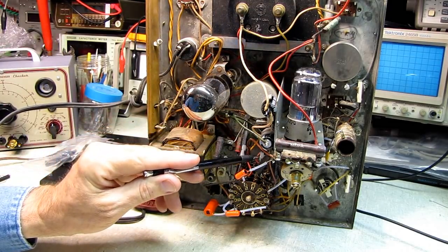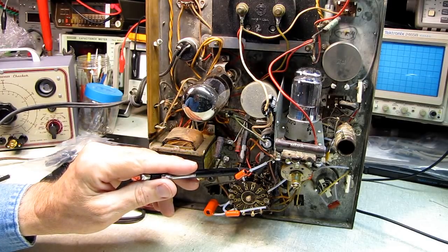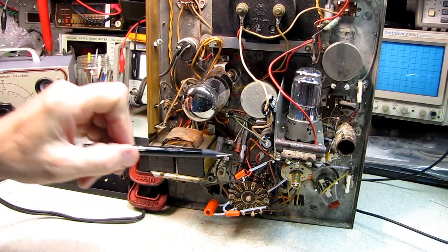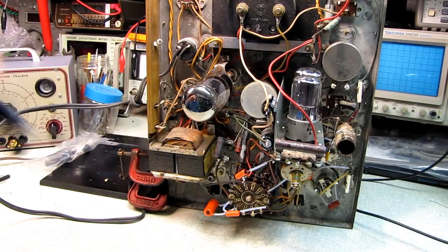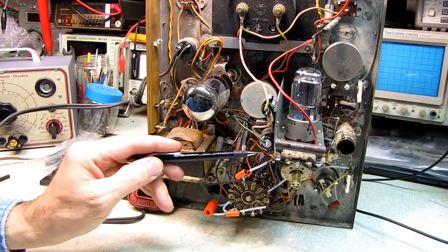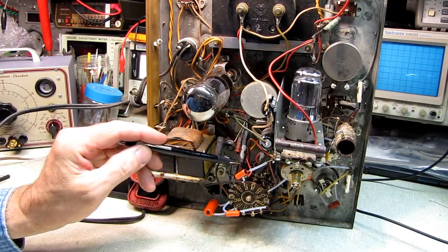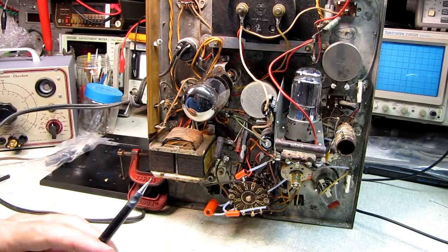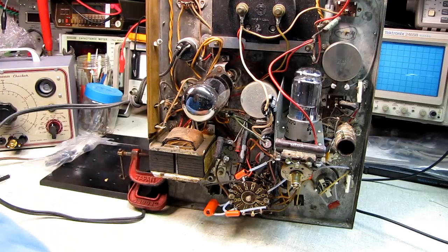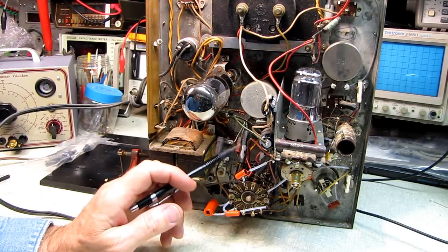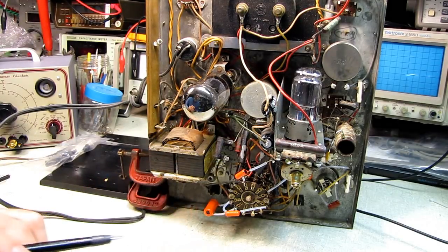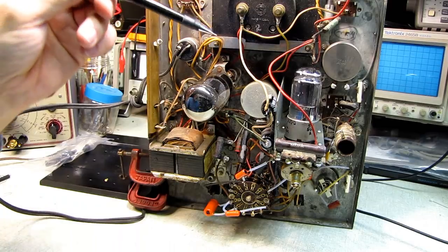If I've got a 2 meg resistor, I'll put 2 1 megs in series. If I've got a 10 meg resistor, I'll put probably 2 5 megs, or say 2 4s and a 2 or something. I'll just total everything up and put them in series so that I've got the insulation resistance, or the low leakage path, and I can use some good high precision metal film resistors to replace these, because some of these, like I say, are 50% out of tolerance.